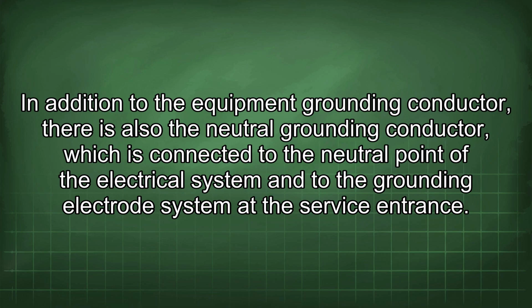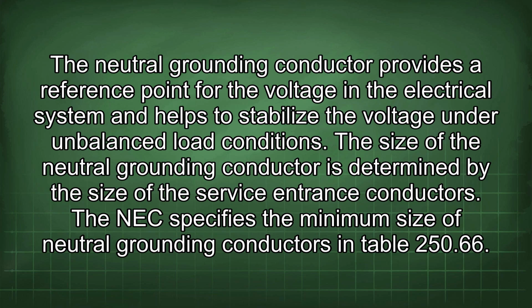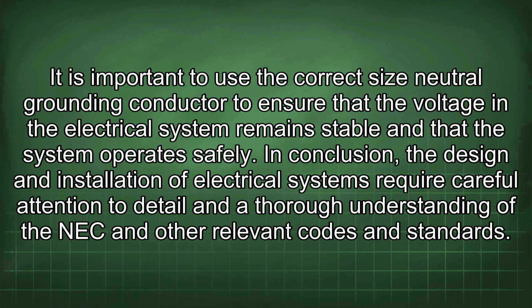In addition to the equipment grounding conductor, there is also the neutral grounding conductor, which is connected to the neutral point of the electrical system and to the grounding electrode system at the service entrance. The neutral grounding conductor provides a reference point for the voltage in the electrical system and helps to stabilize the voltage under unbalanced load conditions. The size of the neutral grounding conductor is determined by the size of the service entrance conductors. The NEC specifies the minimum size of neutral grounding conductors in Table 250.66. It is important to use the correct size neutral grounding conductor to ensure that the voltage in the electrical system remains stable and that the system operates safely.